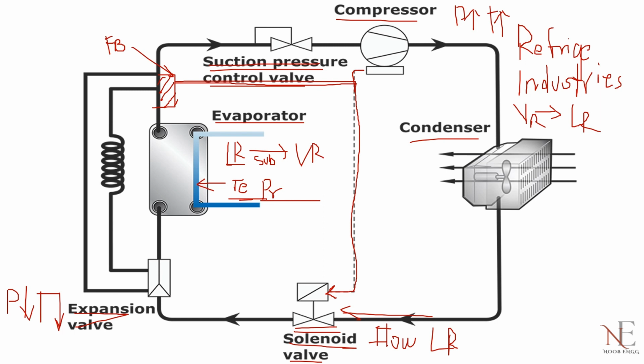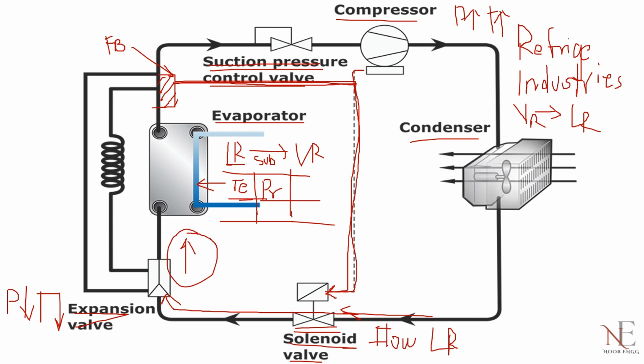As the pressure decreases, the temperature decreases, the pressure decreases in the feeler bulb. The feeler bulb senses the temperature decrease and the decrease in pressure, and the sensing element sends a signal to the solenoid valve. The solenoid valve opens, and the liquid refrigerant enters the expansion valve. It moves further and is operated and the work is done. It will maintain the temperature and pressure again, and by this not letting it frost.